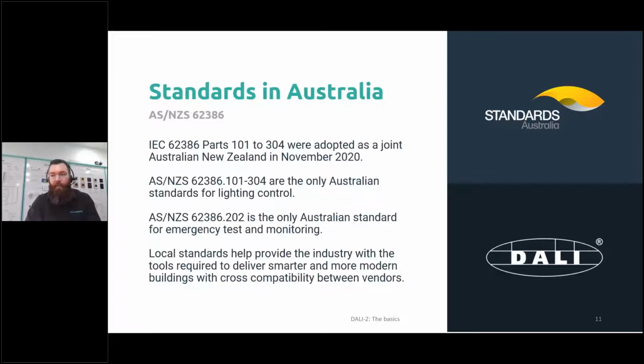It also provides some guidance in procurement, particularly government procurement, towards the type of technologies that should be used in a building to ensure that each of those systems in your lighting control space works together. With adoption of the standard, it's actually a bit of an Australian first—our first Australian standard for input devices such as sensors and switches. It's also the first Australian standard for emergency test and monitoring, because whilst 2293 describes how an emergency device should work, it does very little to describe that test and monitoring system. This 62386 Part 202 steps in to fill that role.